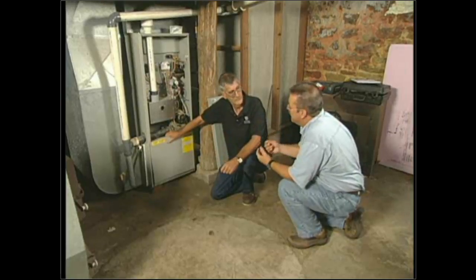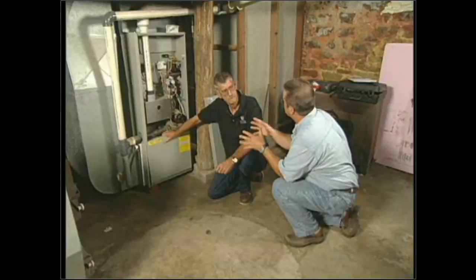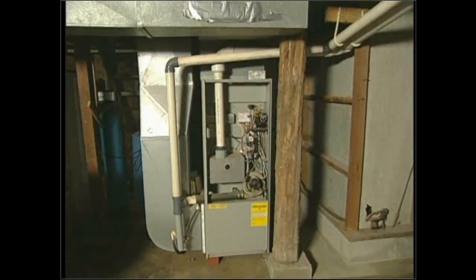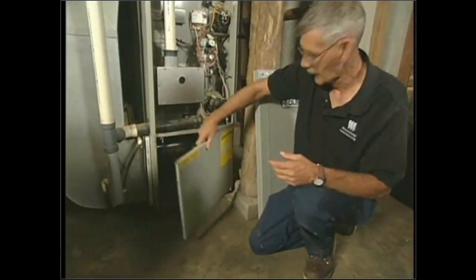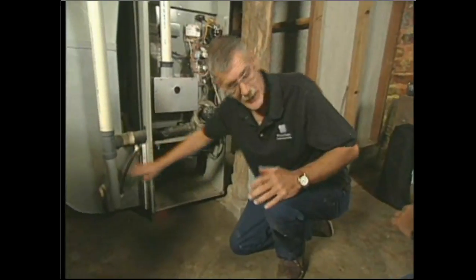Really what you're saying is: before you start any diagnostic testing, take a good look at it — see if the furnace is talking to you. The more audits you do, the more familiar you become. Then I'll pop the lower section open and look for rust and water on the bottom. I'll also look for soot in the condensate line — if I see soot there, that's a sign of a plugged or cracked secondary heat exchanger.